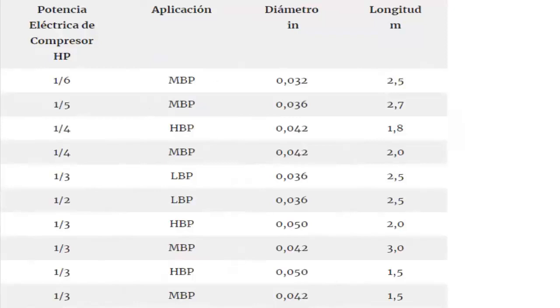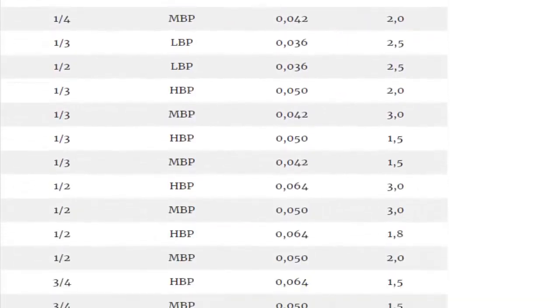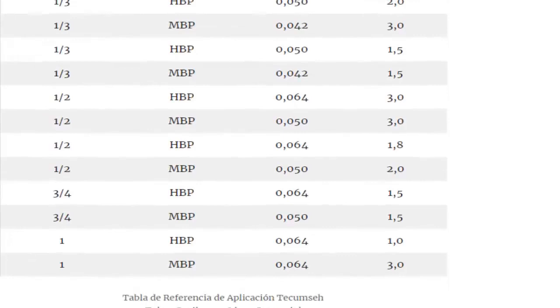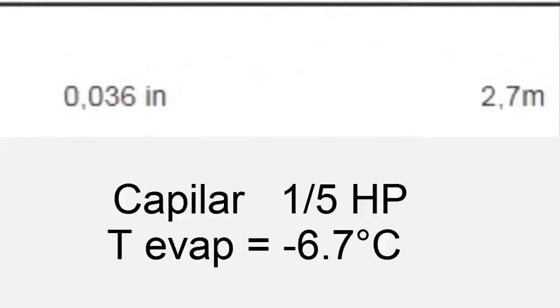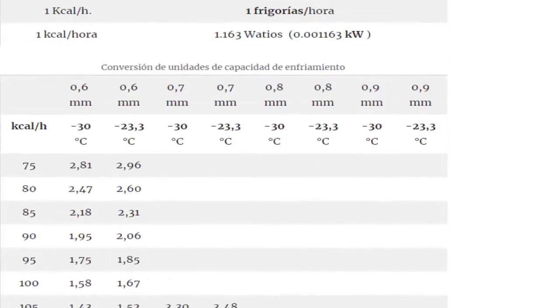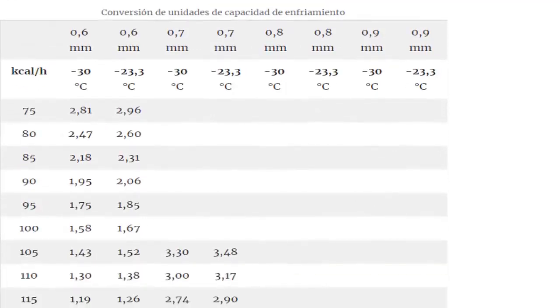On the screen we have the table of capillary sizes for R-134A. This table has been designed only for those cases where you do not know the cooling capacity of the compressor. The table takes as a reference the maximum electrical power emitted by the compressor in HP. We also have a capillary size table for R-134A taking the cooling capacity as a reference.